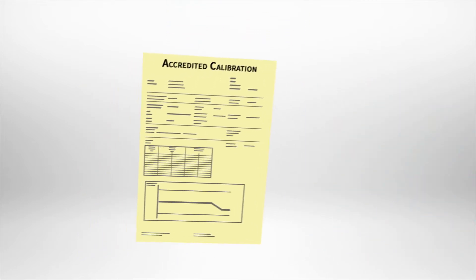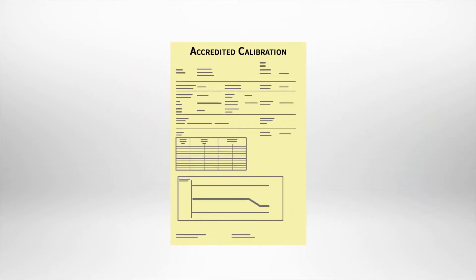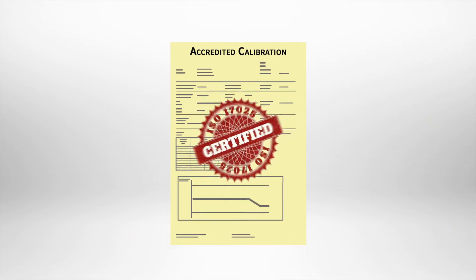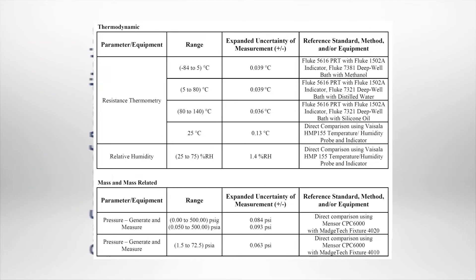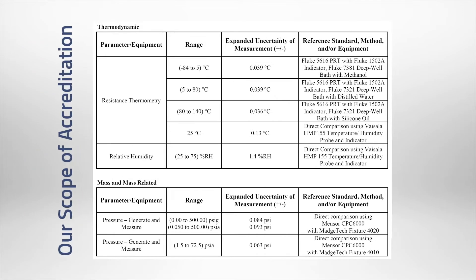An accredited calibration is performed according to standards that are approved by an ISO 17025 accrediting body. Our accrediting body has approved various parameters that we are extremely proficient in. These parameters and values are our scope of accreditation.